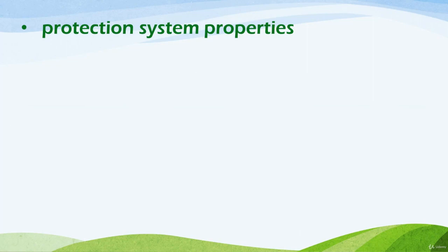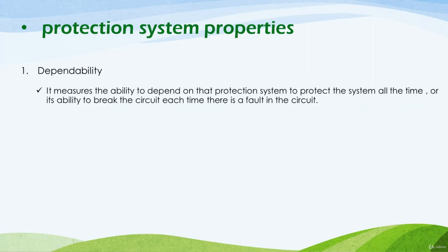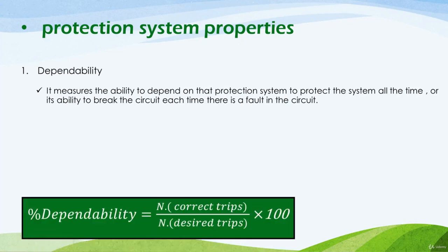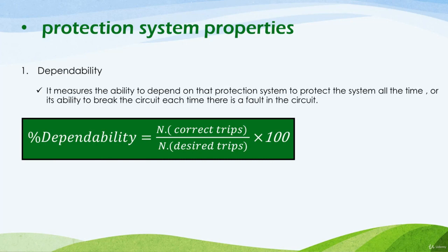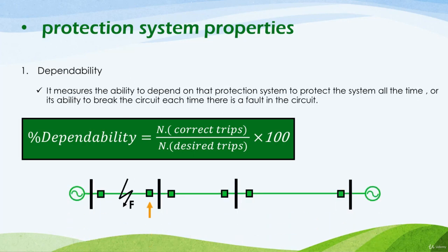Let's start with dependability. Dependability is the ability of the protection system to break the circuit whenever there is a fault. The measure is the number of times the system can clear the fault. It is expressed as a percentage: the number of correct trips when a true fault occurs, divided by the number of desired trips — that is, the total number of times there is a true fault and the circuit must be tripped.